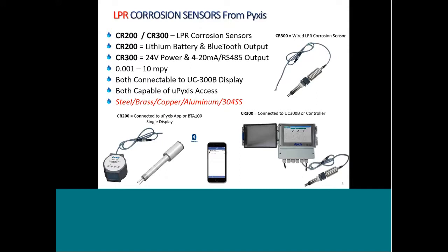In many cases, I've learned even when I was in the water treatment industry, you're kind of cornered into using a corrosion coupon rack in a location of the facility that's convenient for installation purposes, but not necessarily reflective of the most prone areas of corrosion in the operation. And this is where the CR200 technology can truly allow you to provide something to your customer that they otherwise would have never had before.